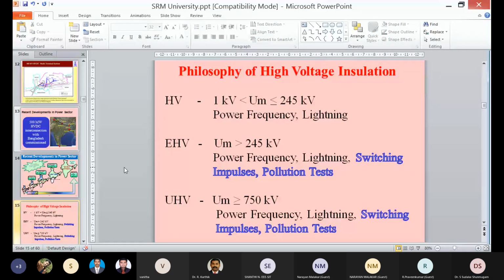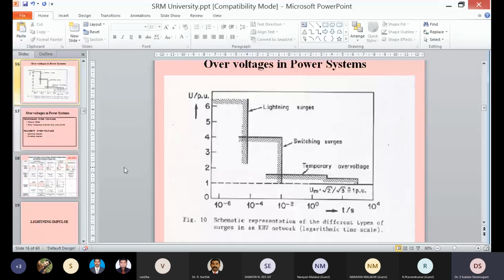Moving on. And what is the level of increase in voltage? In case of temporary overvoltage, that is nothing but power frequency overvoltage. I repeat, power frequency overvoltage is also called temporary overvoltage. The range or the rate of rise of temporary overvoltage will usually be in the range of 1 per unit to 2 per unit.